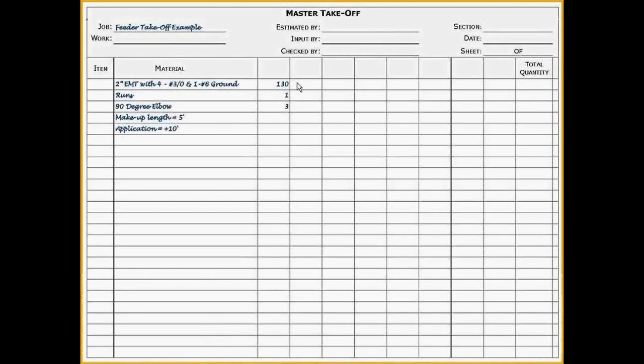Here is an illustration of how you would write it on the takeoff form. 130 feet of 2-inch EMT conduit with 4 number 3-aught coppers and 1 number 6 ground. Runs equals 1.